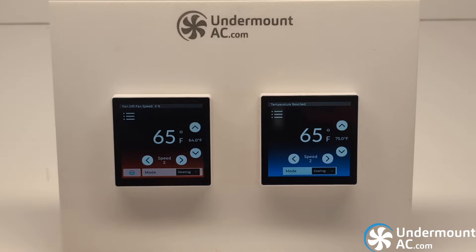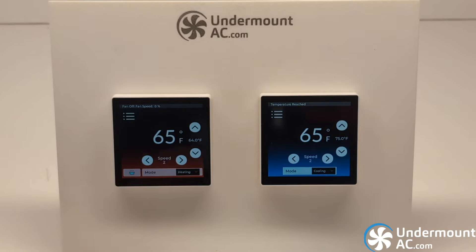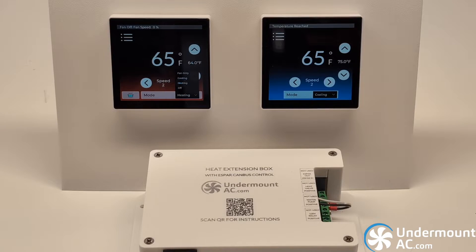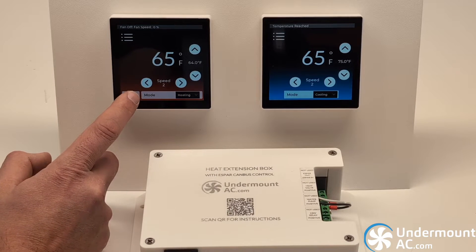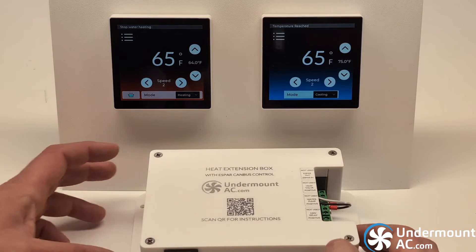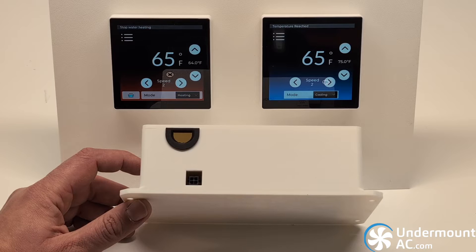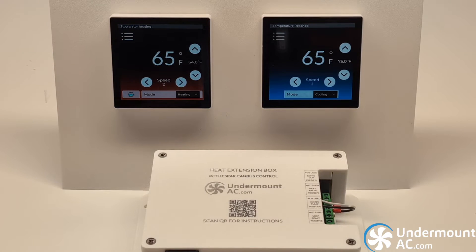The unit on the right is our AC-only unit. It only has cooling and fan functionality and is the standard unit that comes with the kit. The unit on the left will be available shortly in April. It combines cooling and heating functionality. The heat extension box will communicate with the heat thermostat and has four independent relay outputs: one dedicated to a water heater, one to triggering your heater whether it's an Espar or a Webasto — this heat box has a built-in Espar CAN bus module — and another relay for the automatic opening and closing of the heat valve in the HVAC evaporator.